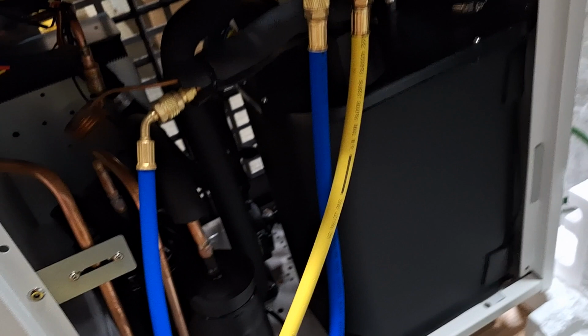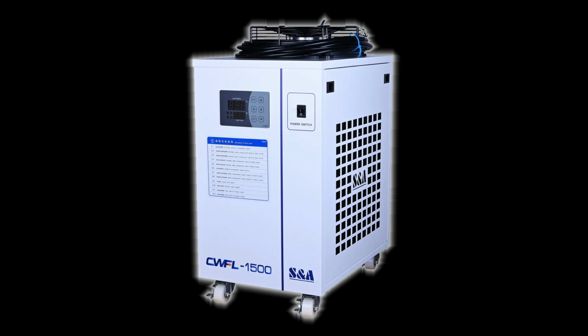One other thing to note, when you are letting the gas out from the manifold gauge into the chiller, loosen up the blue hose end that's connected to the chiller. Loosen that up a little bit so it's not completely pressing in on the Schrader valve, and let a little bit of gas out, and then tighten it up once you get just half a second of gas out. That will prevent any air from getting into the chiller's lines, and the air is definitely something you don't want in there. If you followed all the steps and you did everything right, you should be good to go now.